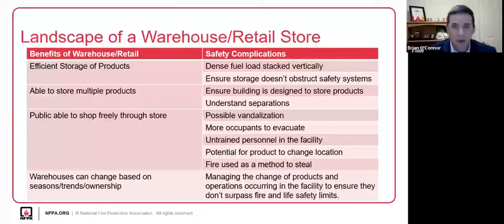When we're stacking and storing all of our goods and materials, we really need to make sure the storage does not obstruct our safety systems. That means we're not obstructing means of egress, ways to get out of the building, and we're not obstructing sprinkler discharge. The sprinkler needs to be able to reach where a fire might happen, so if we stack boxes too closely to them, that could become an obstruction, preventing discharge from reaching the fuel load, and allowing that fire to grow quicker than the sprinkler can keep up with. So there are a lot of considerations to look at when we're looking at the storage of products.